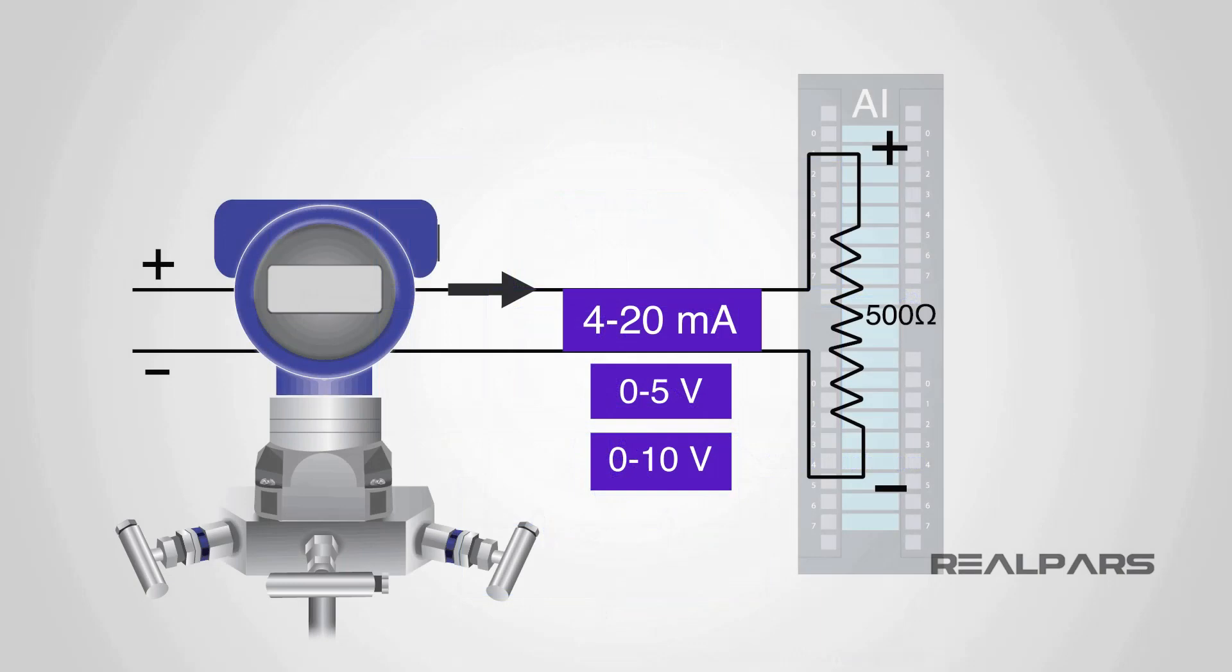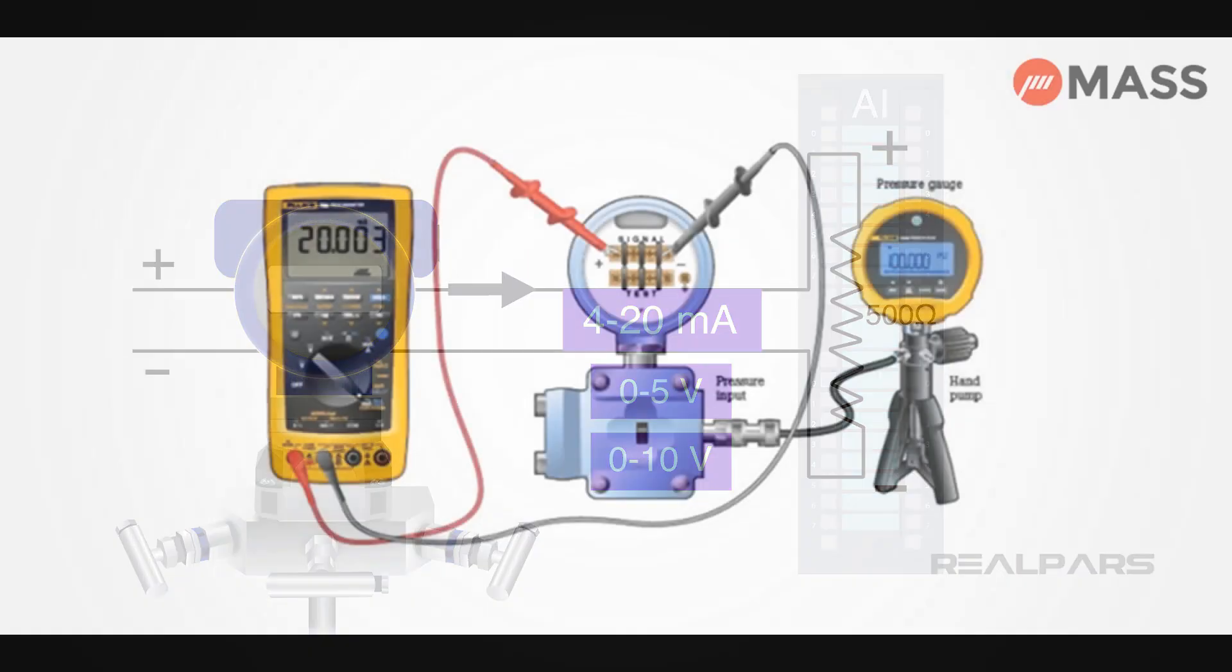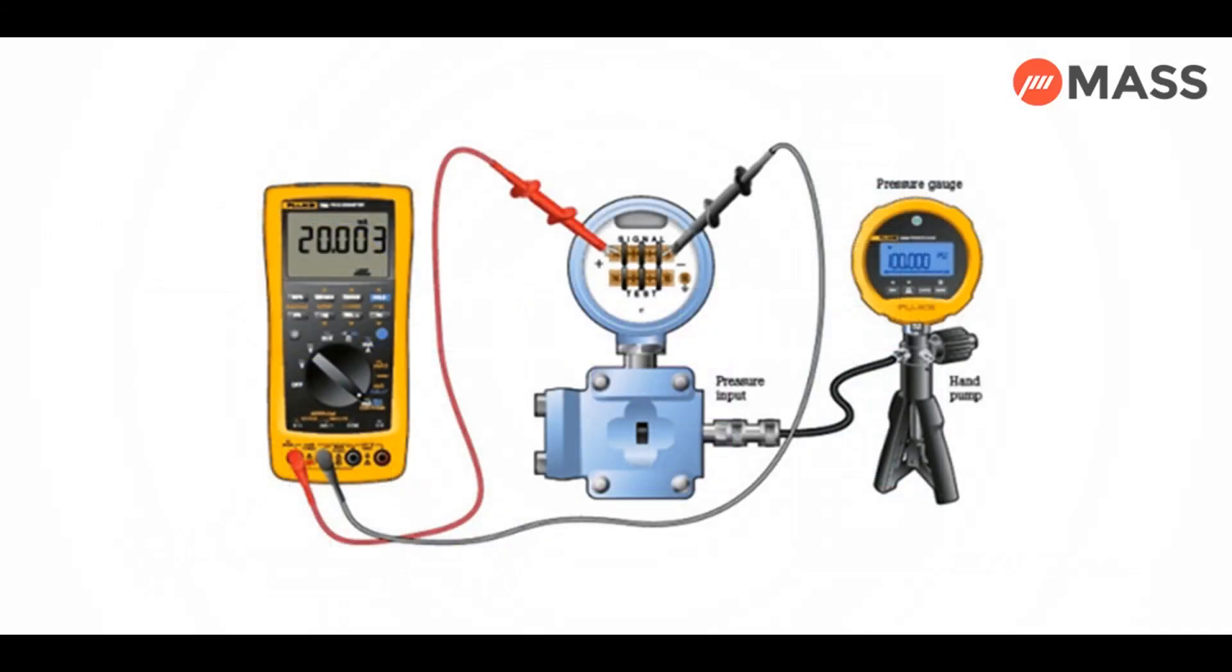The electrical signals from the high side and the low side pressure sensors are then processed by the transmitter's electronics. The transmitter calculates the differential pressure based on the difference between the signals from the two sensors. The differential pressure is then converted into an output signal, often a 4 to 20 mA current signal or other standardized signal. The DP transmitter is calibrated to ensure its output signal accurately represents the differential pressure and, by extension, the flow rate.